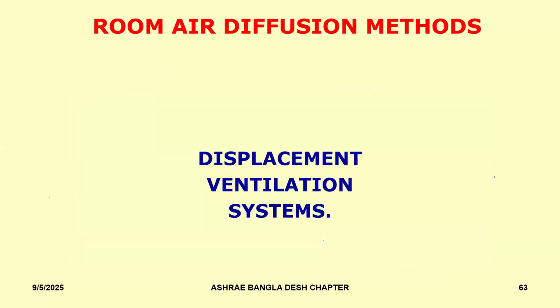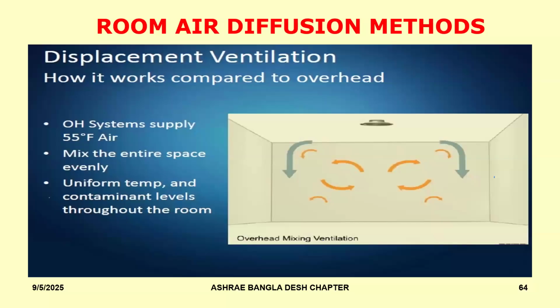Now we come to the next type of air distribution system, which we call the displacement ventilation system. How does this really work? Now, what you see in this room is a typical overhead mixing system. So there is an outlet diffuser which is placed on the ceiling. The air exits, comes like that from all the sides and mixes with the room air. Typically, we supply the air at a temperature of around 55 degrees Fahrenheit to keep your room at about 75 degrees Fahrenheit. And the outlet velocity is high, and the air is supplied from a point which is far away from the occupied zone. Typically, the occupied zone would be up to a height of about 6 feet from the floor level, and the air outlet is installed at the ceiling level, maybe about 12, 13, or 14 feet. So that's how a mixing air system works.